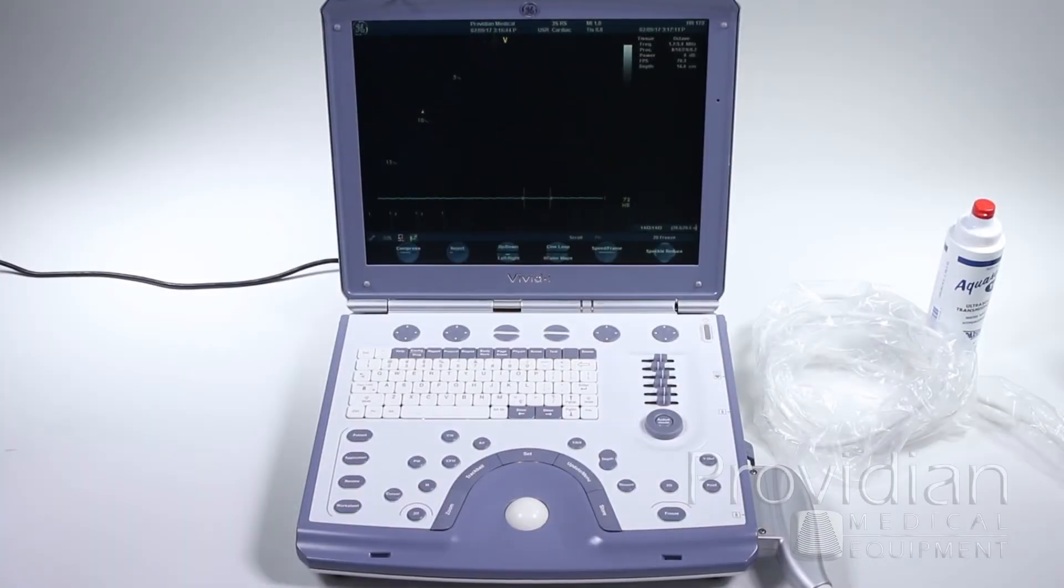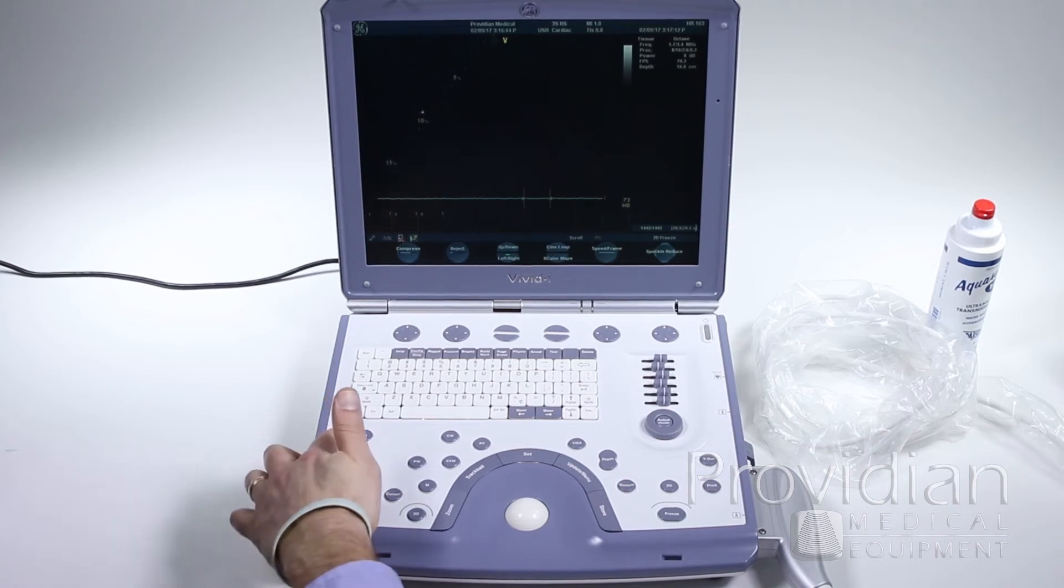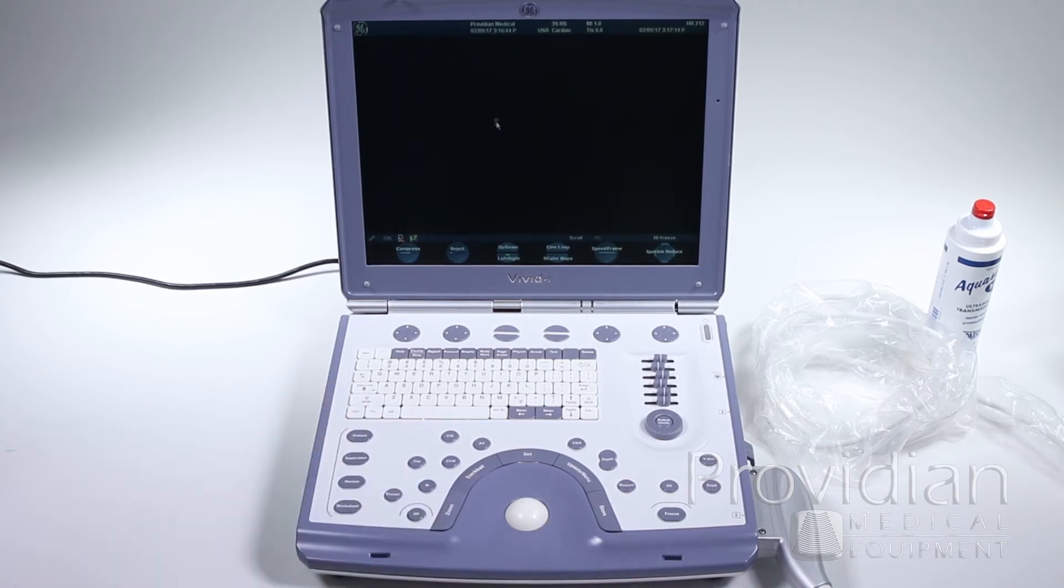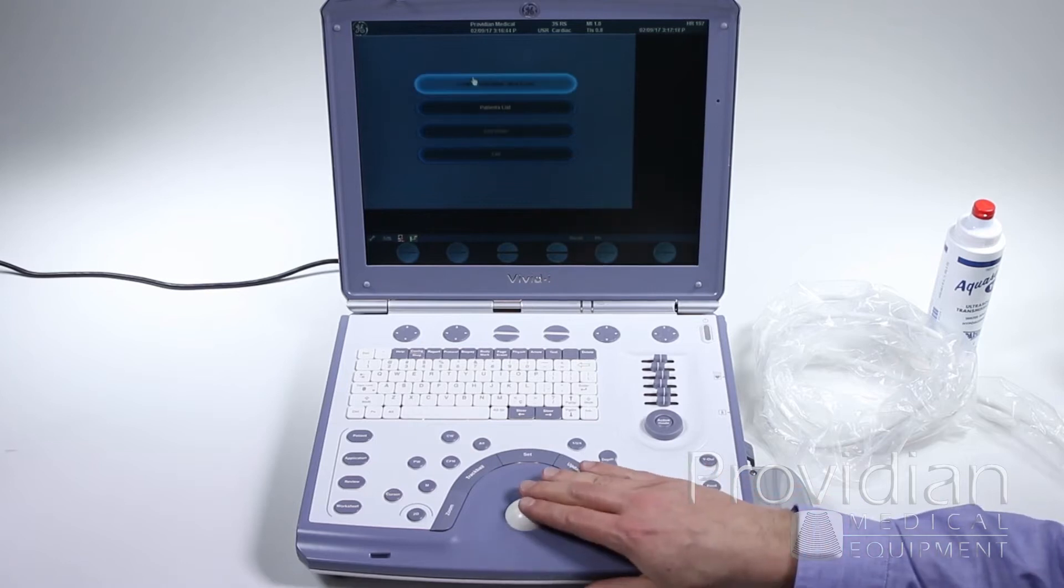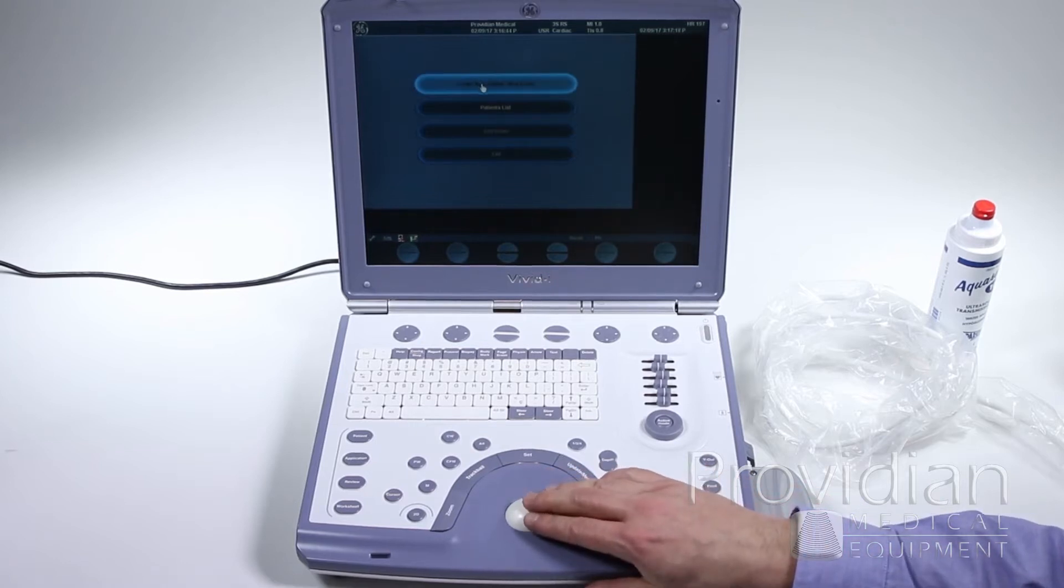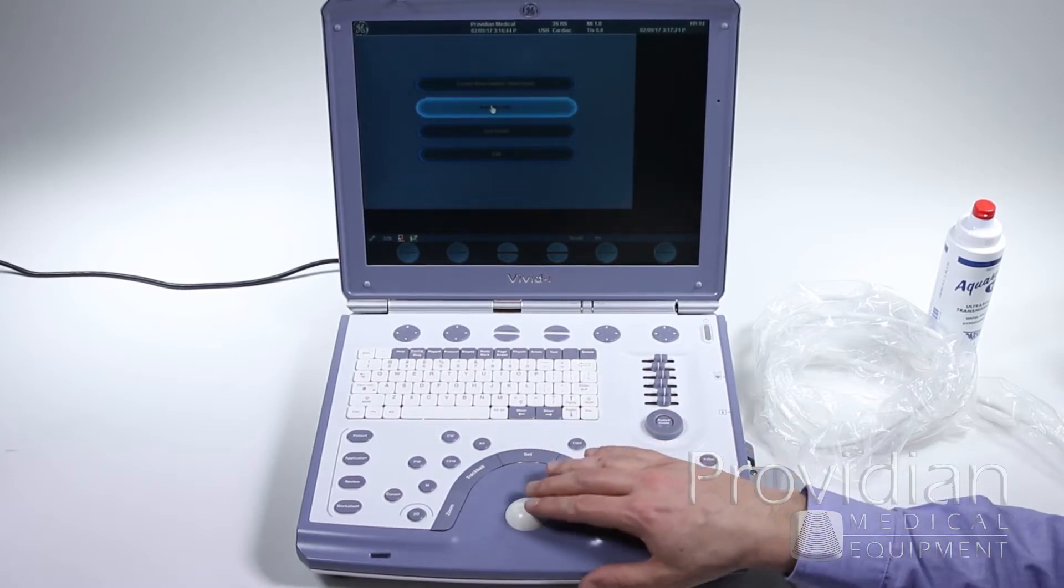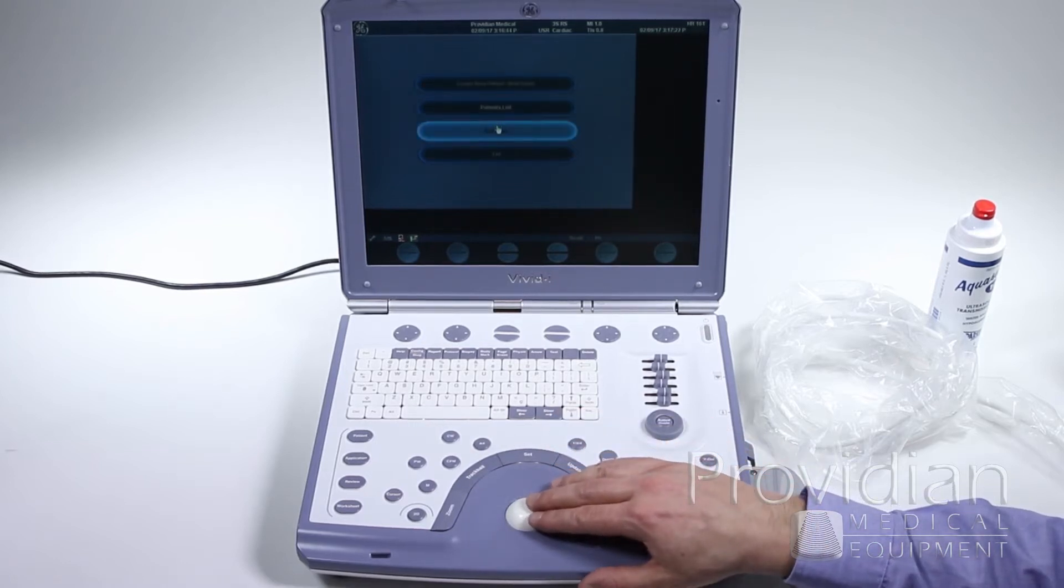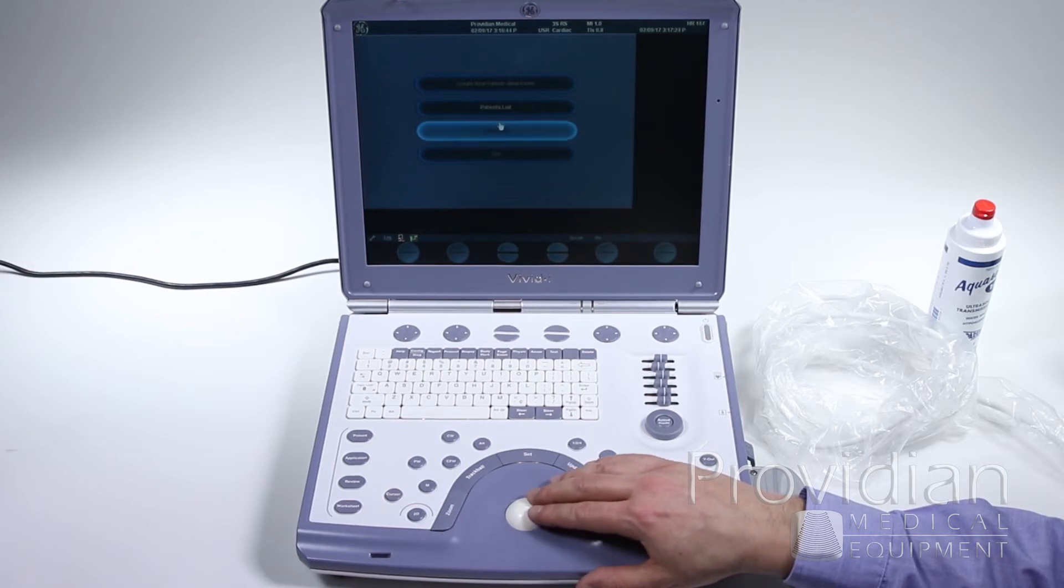To begin imaging with the Vivid i, we're going to start over here on the left-hand side. We're going to click patient to add a new patient, and it's going to give me a menu. Do I want to create a new patient or a new exam? See my existing patient list, end the current exam, or just exit if I made a mistake.